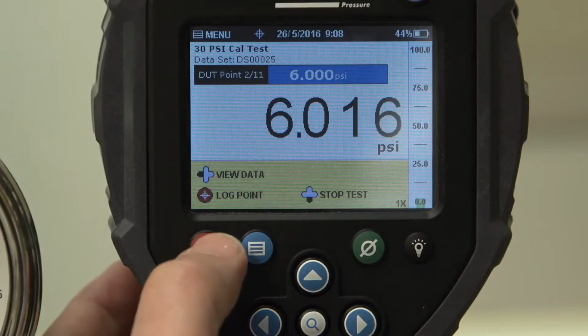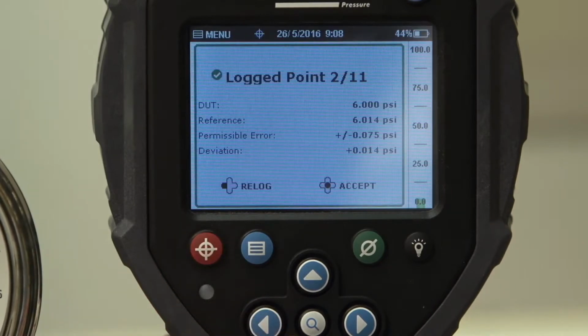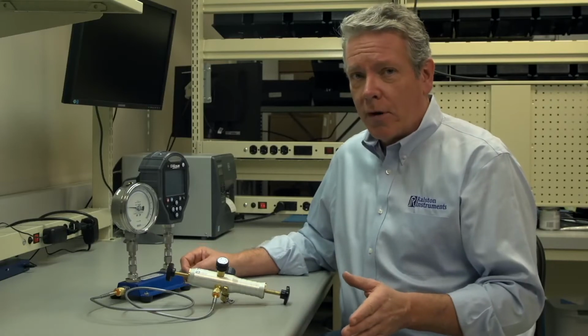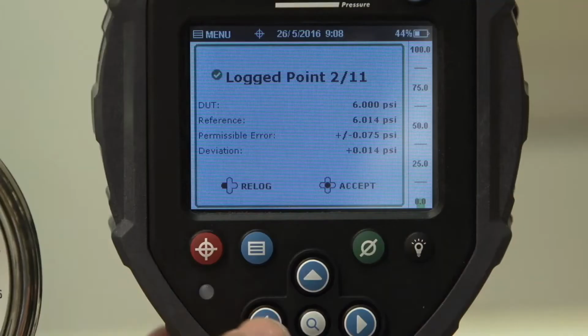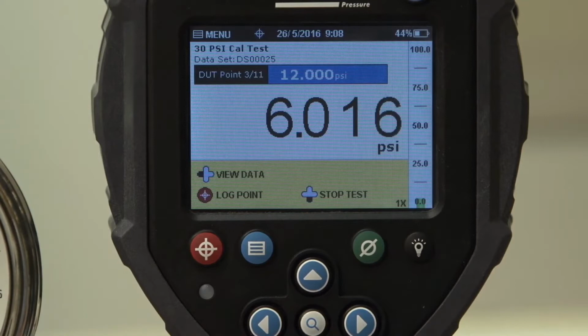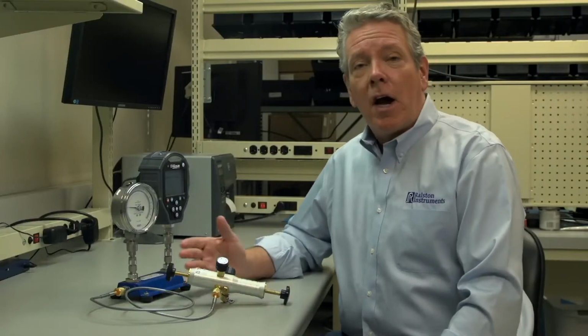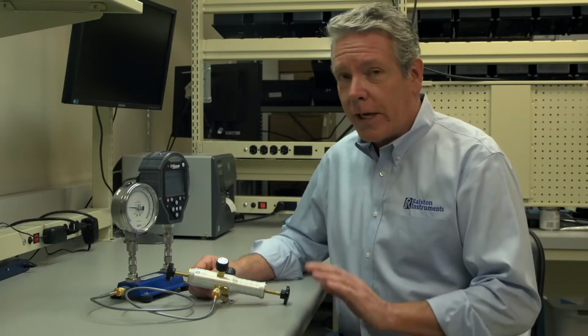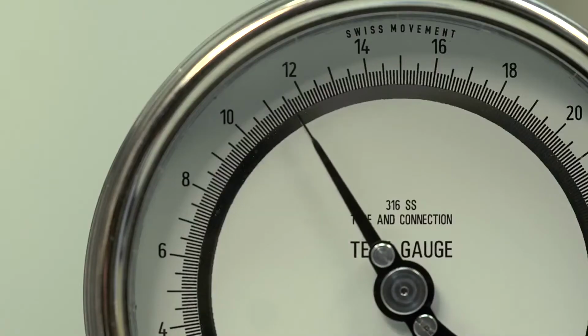So now we press log and you see a summary of the test point. Notice that both the reference and DUT readings are logged along with the computed deviation. We can also see that this point was outside the permissible error for this device. You can now accept this reading, or you can redo the test point. But if you're confident in the reading, then you can just press accept, and the actual value will be saved for that test point. We then do this up and down the test point scale, with each reading being saved at each test point.